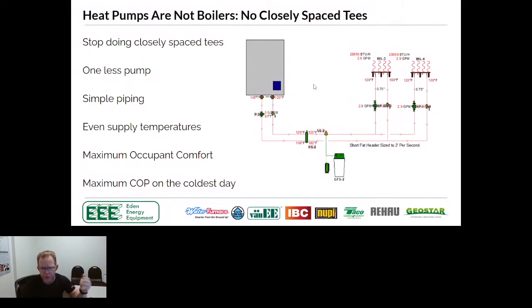Moving on from that, this is a pretty good example of how you would want to do that. So, a nice little short fat header. We're going to show you in a second what that looks like in our live fire lab. It's very simple piping. It's one less pump. It's very easy to remember. Basically, the common piping, where you can see my mouse moving here, we want to make sure that common piping is sized for less than 2 feet per second.